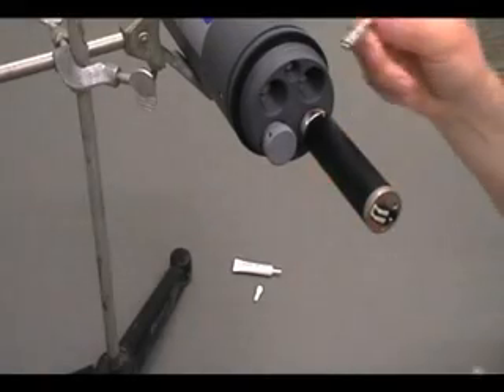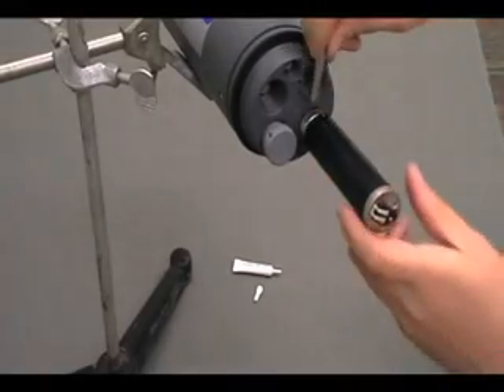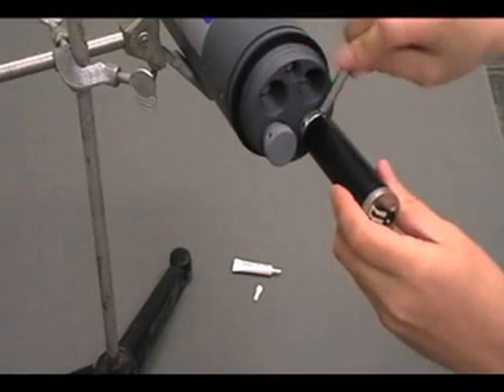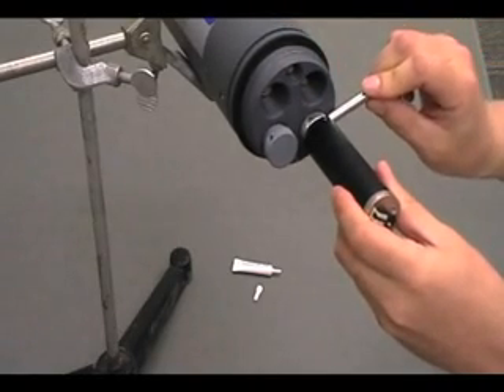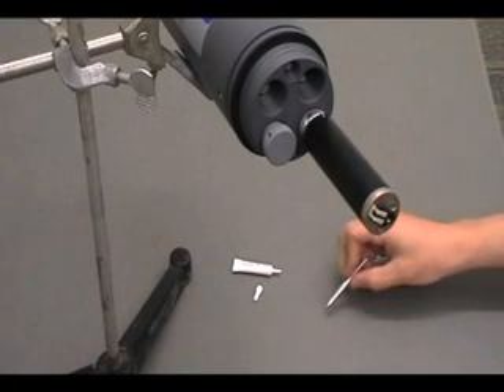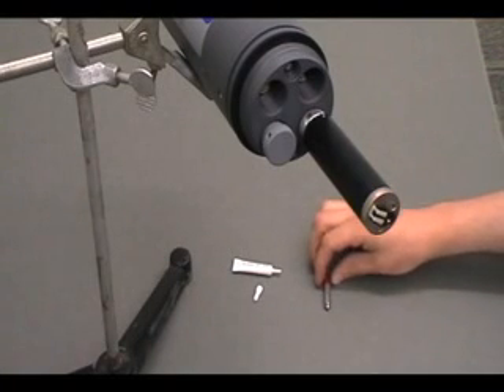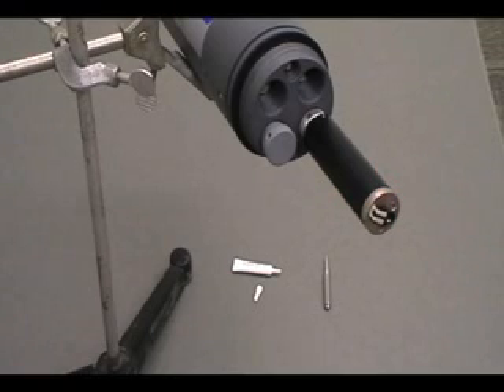Finish tightening using the short end of the installation tool so that the seal is waterproof. Do not over-tighten. When tightened properly, it is normal for there to still be a 1 to 2 millimeter gap between the nut of the optical sensor and the body of the bulkhead. Install the optical chlorophyll and optical turbidity sensors in the same manner.